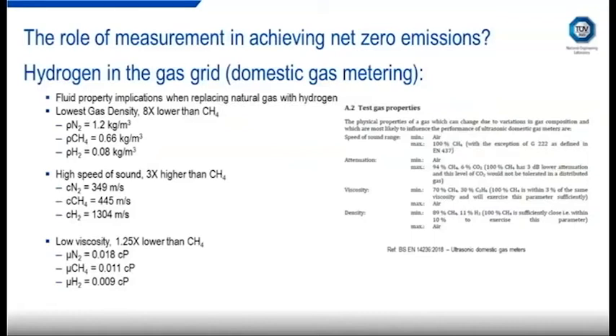You can see on the right-hand side, this is a screenshot from the standard for ultrasonic domestic gas meters, and these are recommended test gases that are currently used. And you can see there's nothing in there that really represents hydrogen or something close to a pure hydrogen. So there's obviously work that needs to be done on the standards as well as in developing the evidence for the performance of each technology.